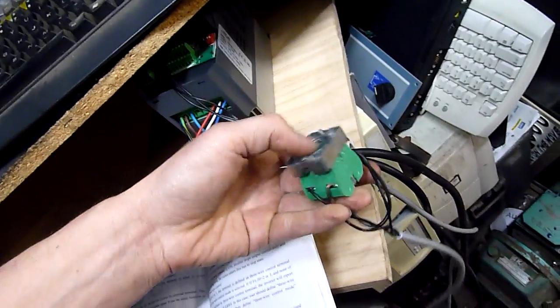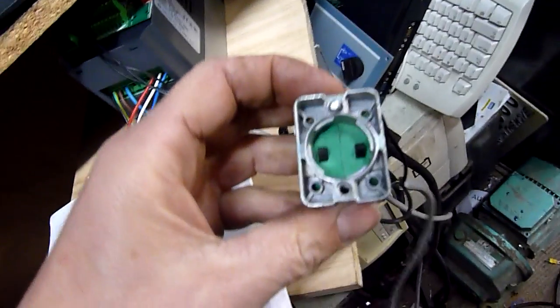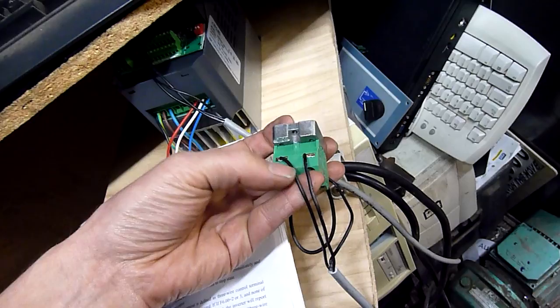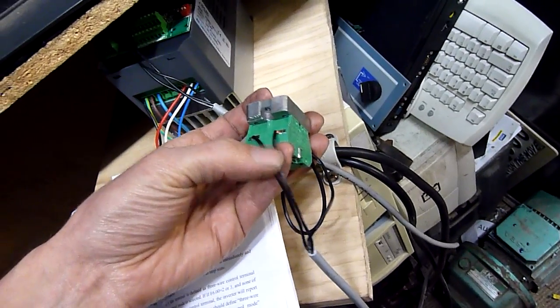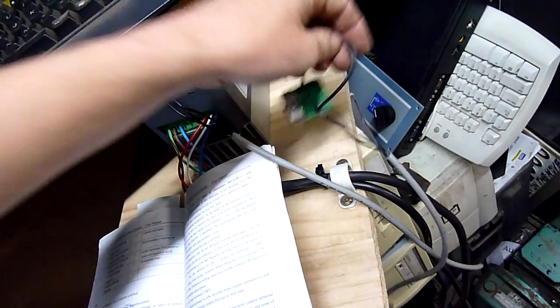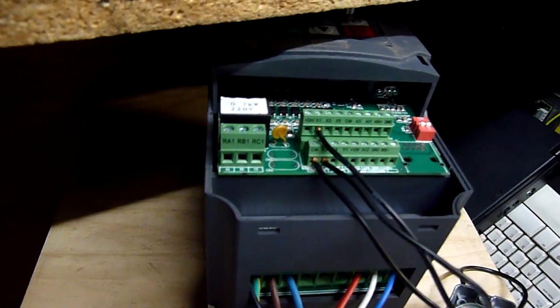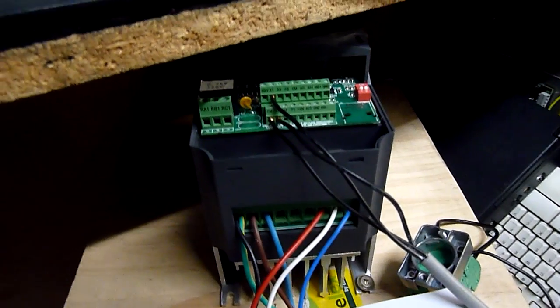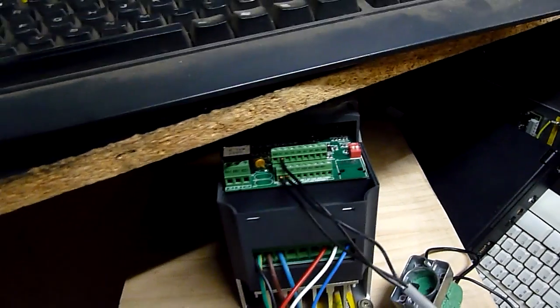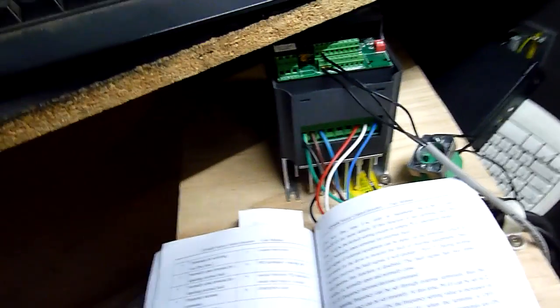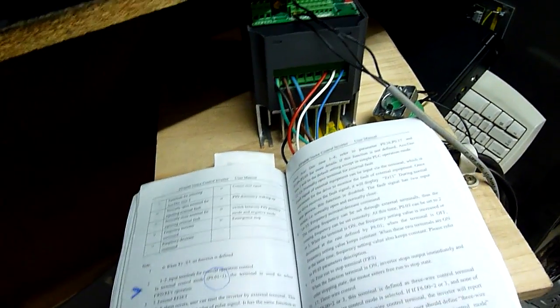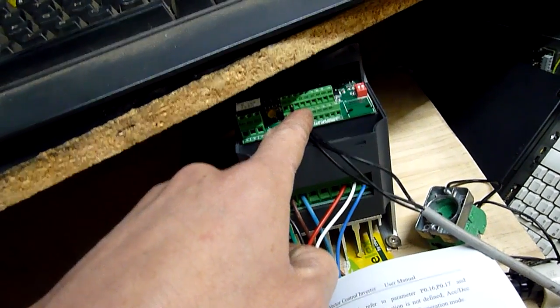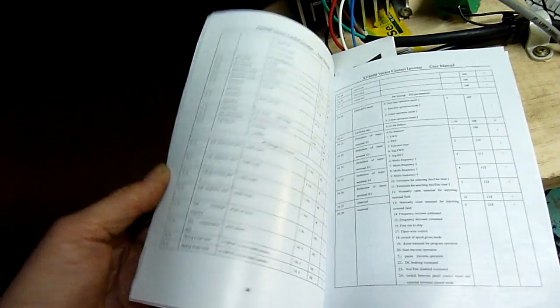Yeah, they're just two momentary switches, that's all you need, you can just bridge out common. Line 3 goes to CM on the header, and then these go to X1 and X2, X1 being forward, X2 being reverse. And that's just your standard negative 24 volt common, it is not positive 24 volt, do not put it to the positive. Just go X1 for switch 1, X2 for switch 2, and CM for common. And both of these CMs here and here are linked together, they're the same common, they just give you two ports to run extra common wires off, or even run it to a terminal strip and branch off from there. You can do whatever wiring you want outside of it, and they've given you adequate connections, up to X5. X1 to X5 are all programmable digital inputs on these drives.